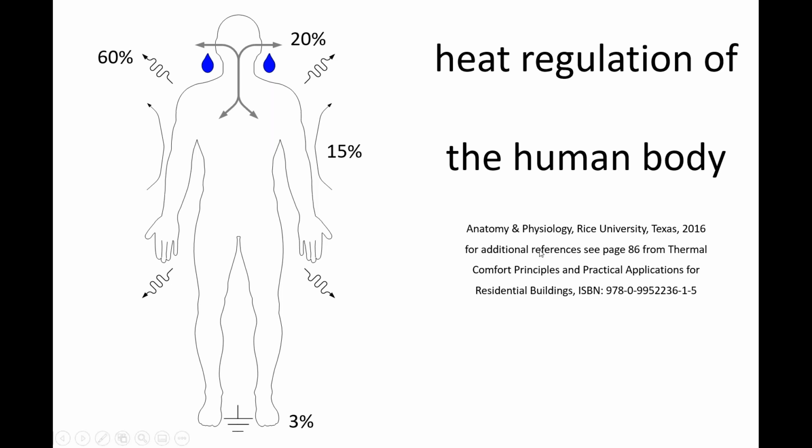One of the areas of debate has to do with the human body and the regulation of temperature. And it's quite interesting because even within ASHRAE's own library, there is a conflict between the numbers. But if you look at the medical textbooks, you look at the ASHRAE handbooks, if you look at the indoor environmental guidebooks, you will find that it will tell you that the dominant mechanism that the human regulates its temperature, sensing and releasing, is through radiation. And so this is why enclosure design is so important, because as practicing engineers and designers, we know that the differential temperature between two surfaces is going to be driven by the Stefan-Boltzmann constant and then also the emissivity and the delta T.